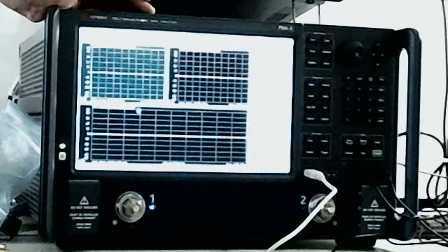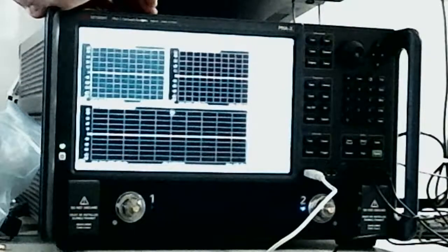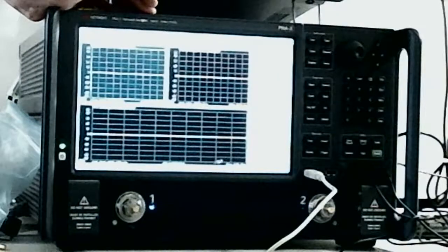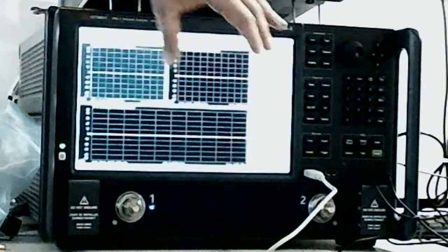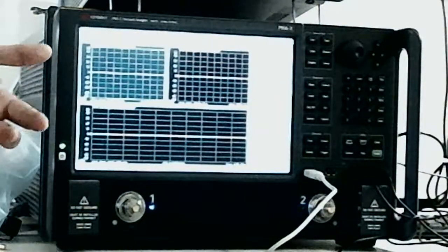That's why I said in the new firmware, what we did is we added something called sheets. What that does, it's like tabs in Excel. So you can actually rename them. So you can say one is 13.5 gig power sweep, 10 gig power sweep. You can call them whatever you want, and then that gives you an idea. Because here, I can look at it and see some of that information, but I don't know which one is which frequency, right? Unless I click on it. So it says here CW 2.4, but if I start putting maybe 8 or so of these, I'm going to have a hard time figuring out which one is which, right? So that's where we're going to do that.